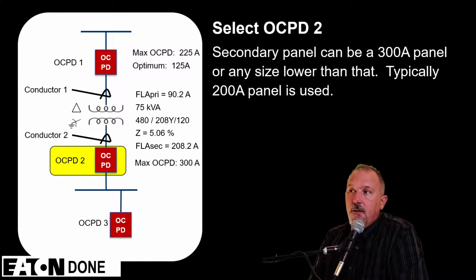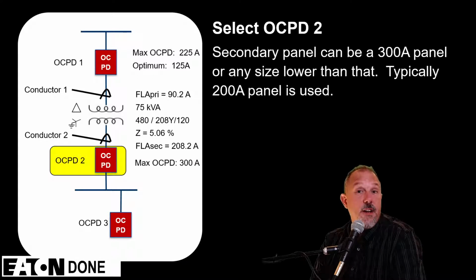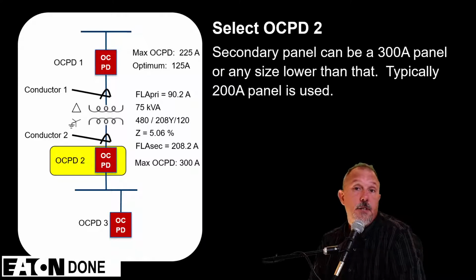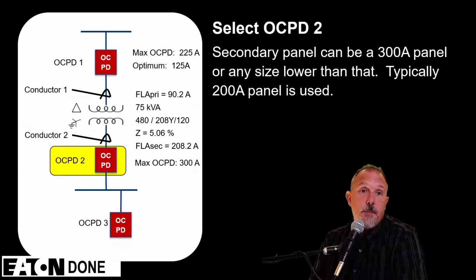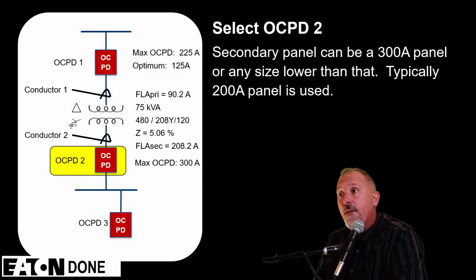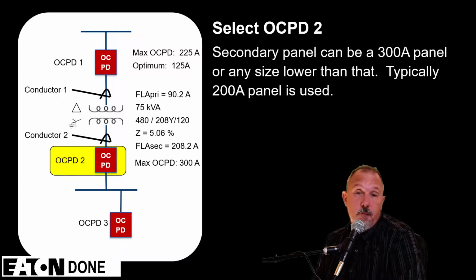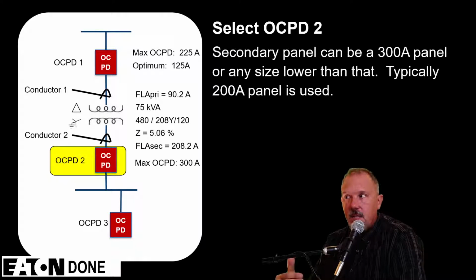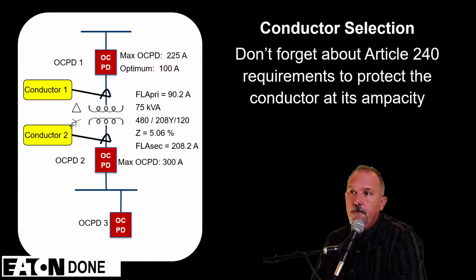Now, the secondary panel could be a 300. Typically, again, I say a 200 amp or a 225 amp panel board. I've had another engineer tell me that he would typically see a 225 amp panel board on the secondary of this 75 kVA transformer. Very common transformer to use. But based upon National Electrical Code requirements, I could put something much larger.